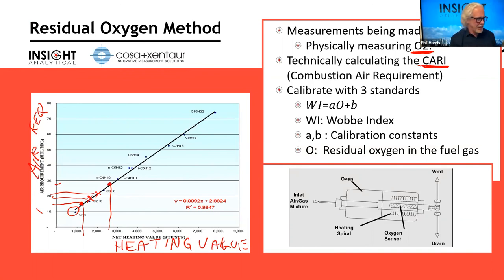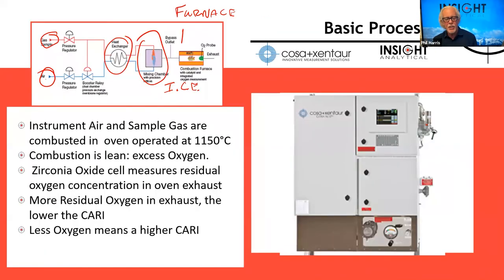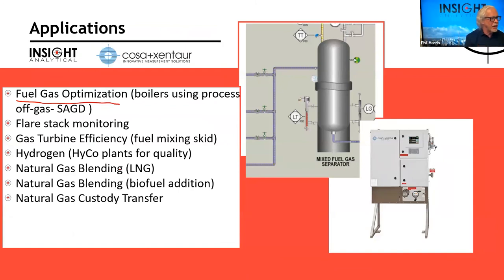Good question about the hydrogen. I'm going to come right back to that one in a second, Lee. So as my fuel changes composition, I'm going to change how much air I need to put to the burner. If I've got any place where I'm generating a fuel gas, it could be a biogas from fermentation, it could be methane off of landfill gas, anything that has varying composition, I want to be able to measure that and optimize how my burner is running. So I can use this to do fuel gas optimizations.